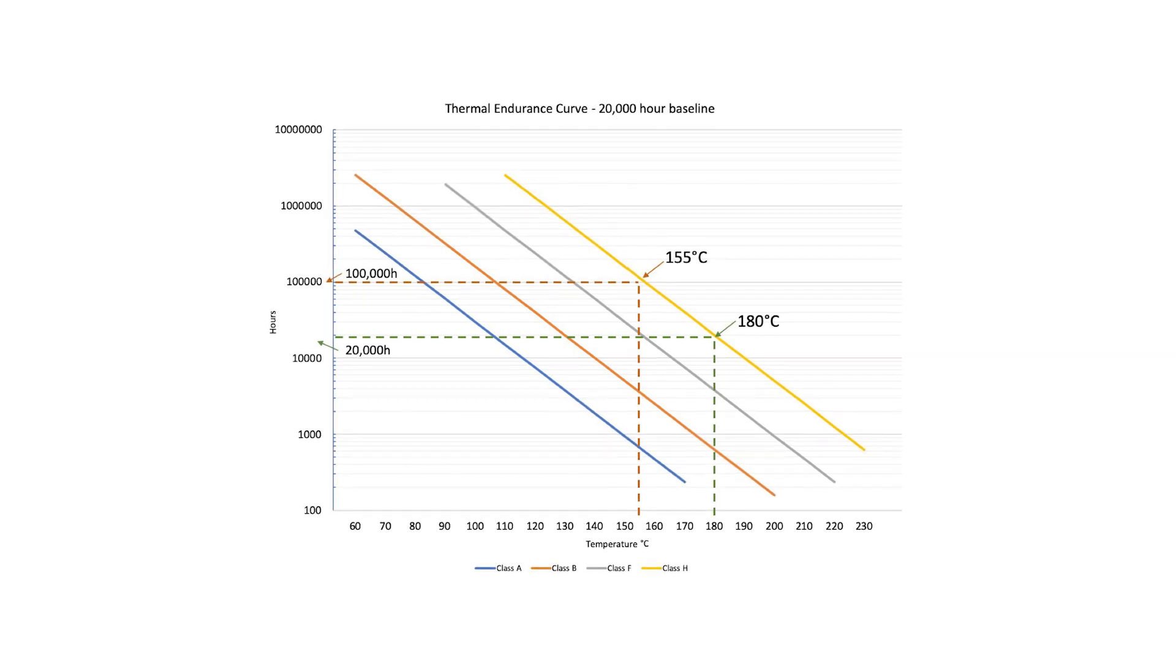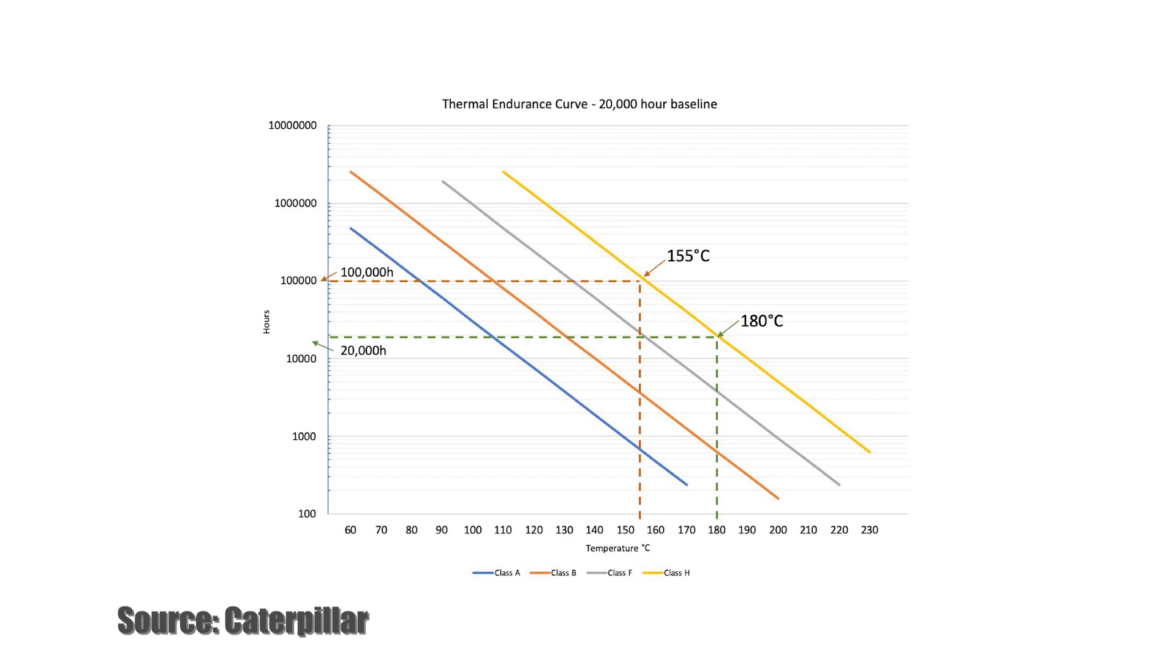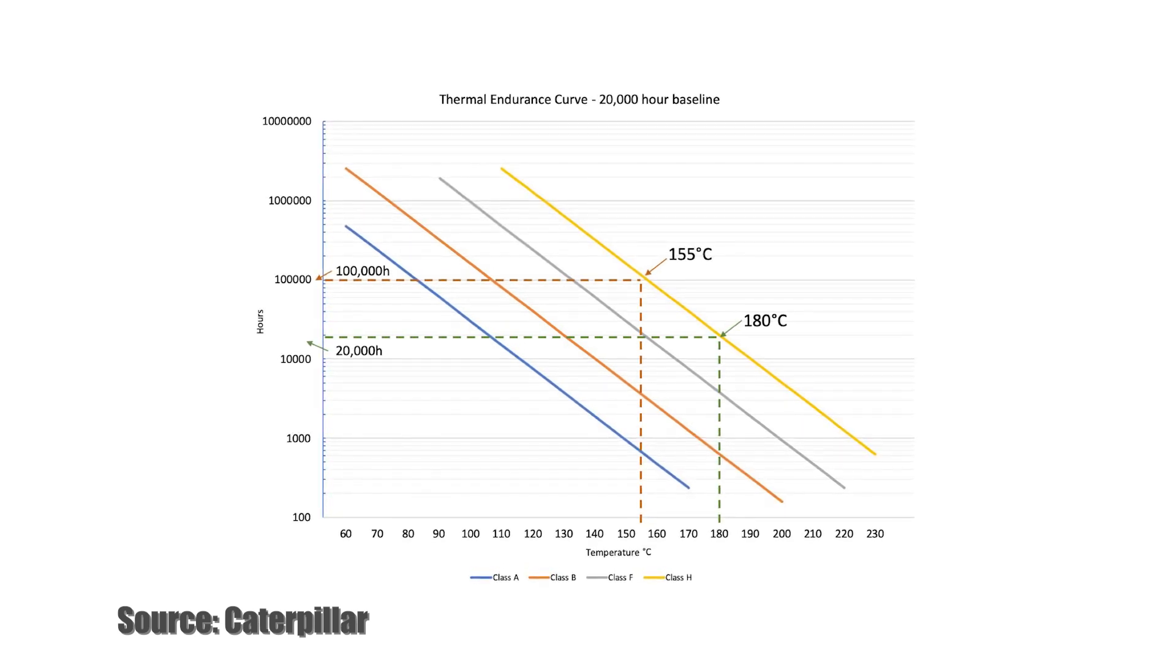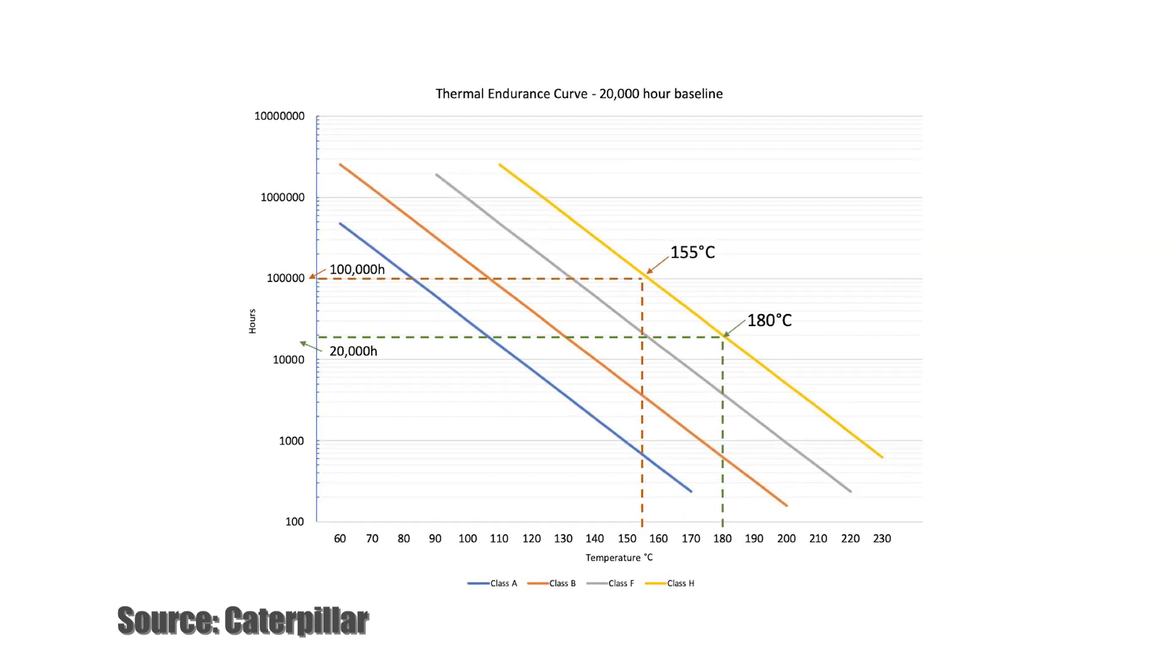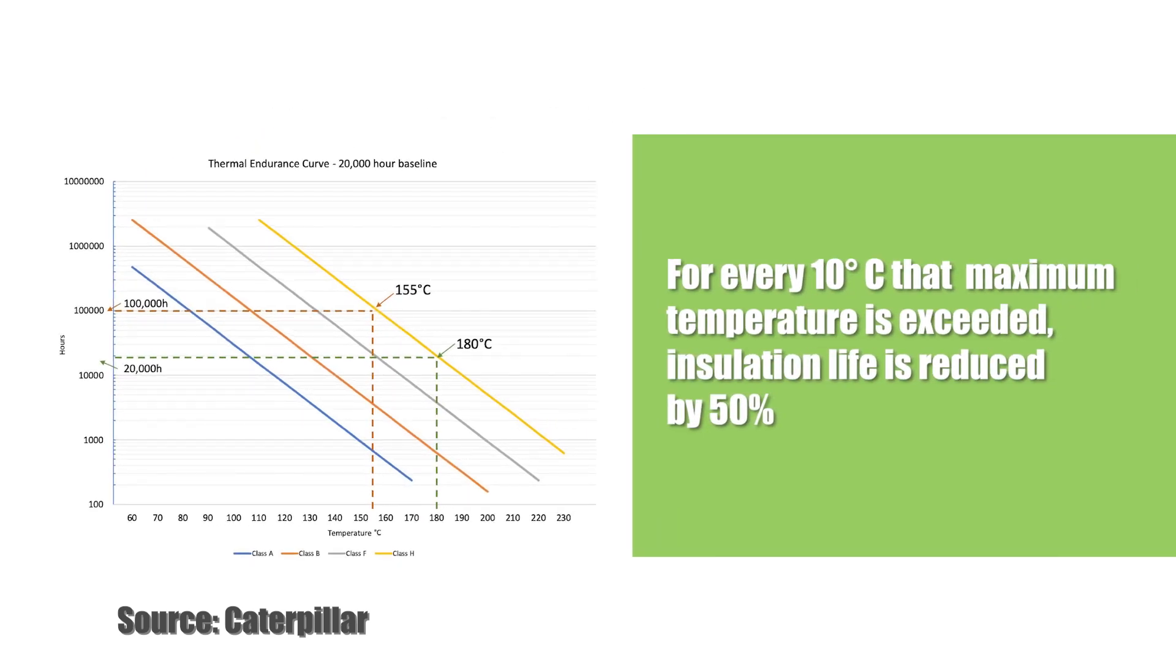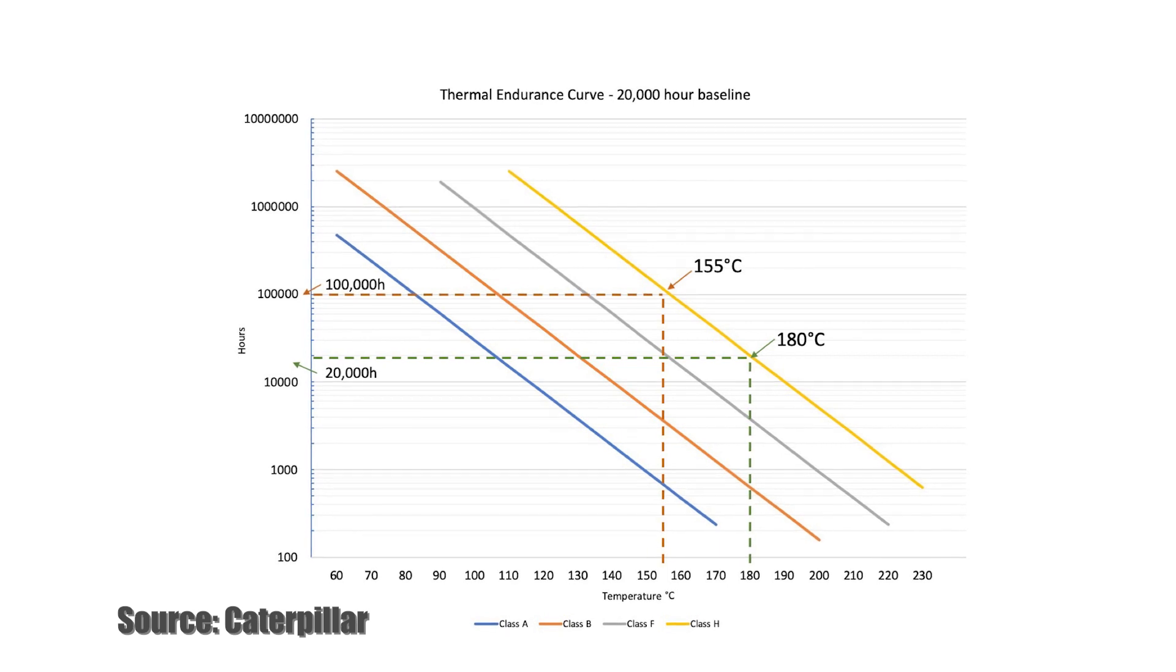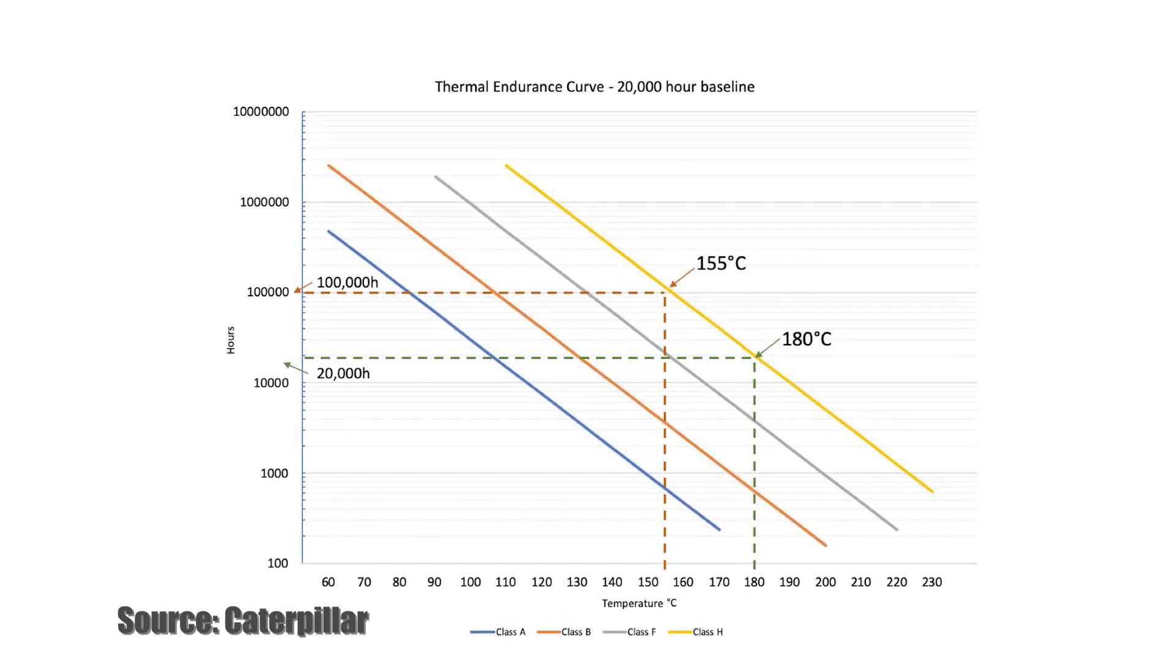The maximum temperature specified by the insulation class will provide an insulation life of 20,000 hours, with the motor operating at full load. According to the Arrhenius equation, which explains that chemical reactions occur more rapidly at higher temperatures, for every 10 degrees C that the maximum temperature is exceeded, the insulation life will be reduced by 50%. Conversely, for every 10 degrees C that the motor is operated below the maximum temperature, the insulation life will be doubled.